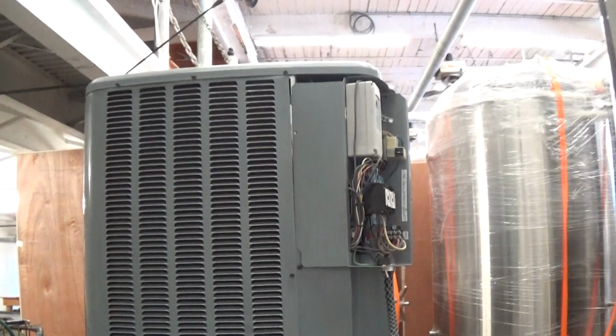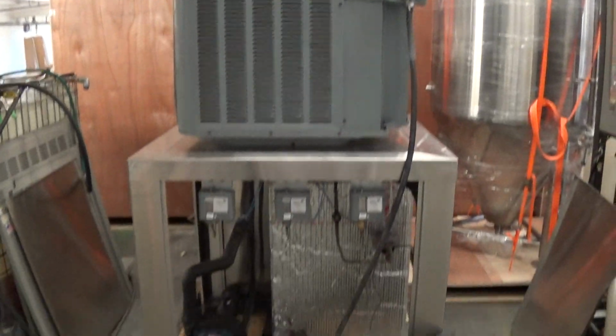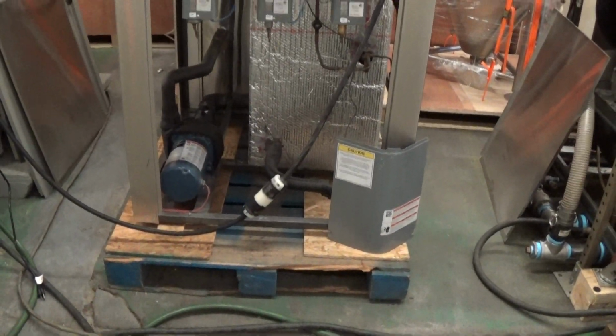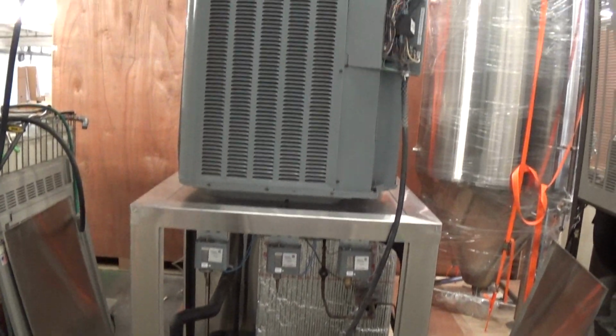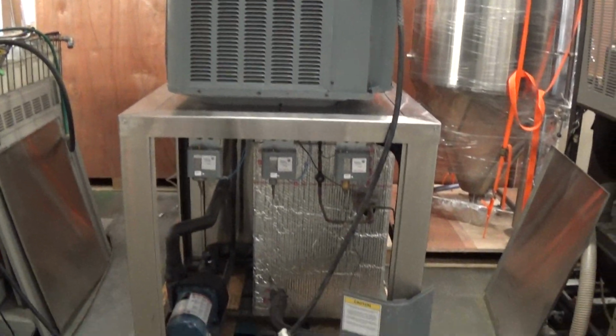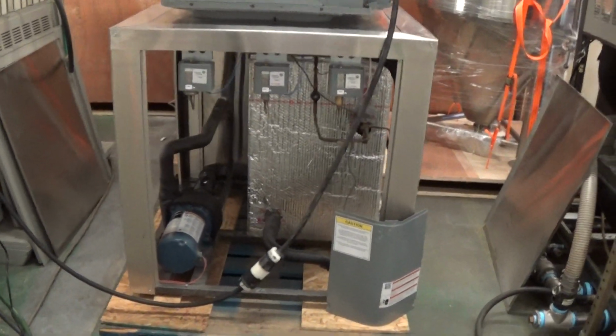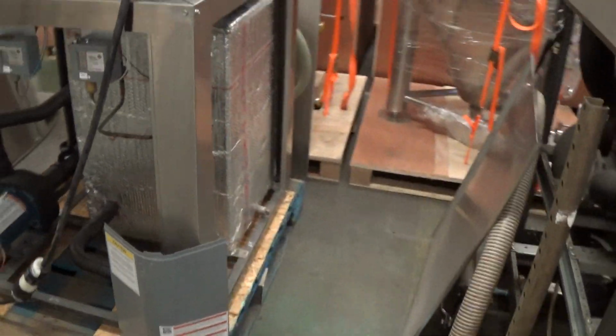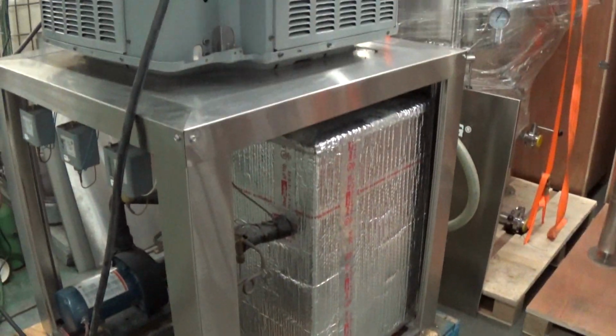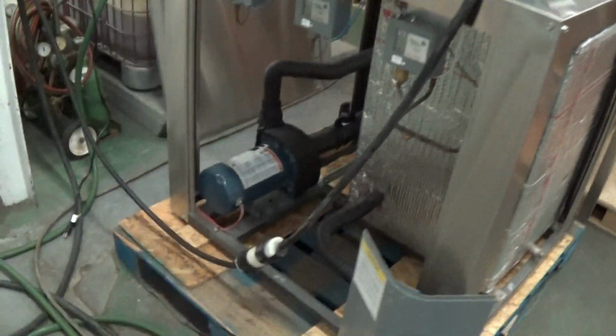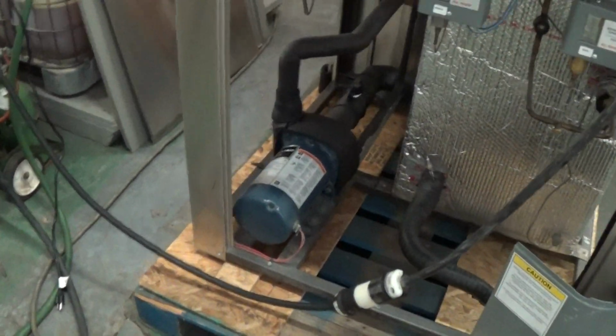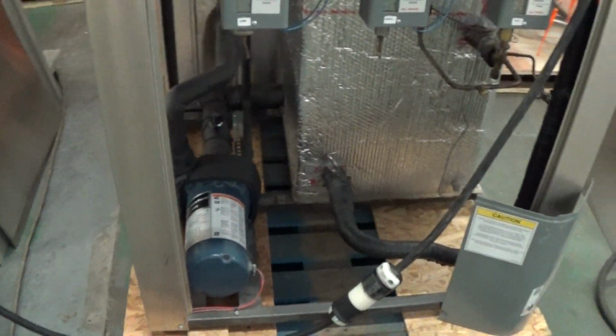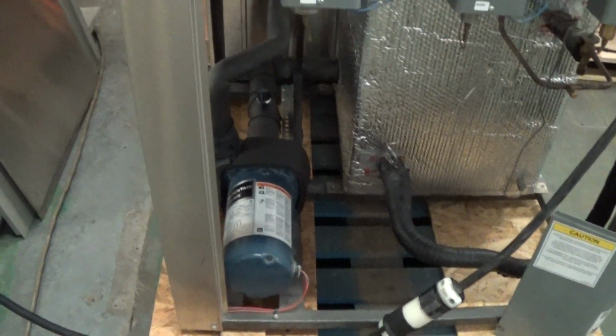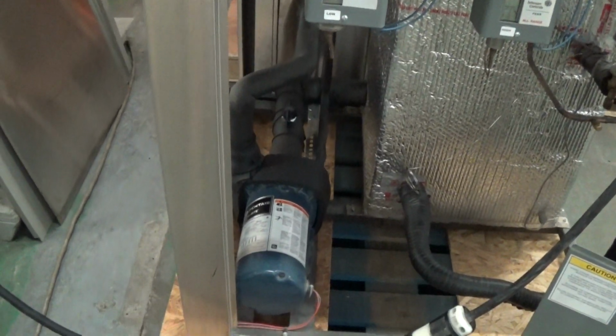The chiller is outdoor rated. Some people do put these indoors. I think its new home is going to be indoors. Very simple, very reliable design. We've provided many of them. In this case, it has a 44-gallon insulated reservoir tank, and it has a 460 volt 3-phase pump. The pump draws from the tank and goes out to the process.